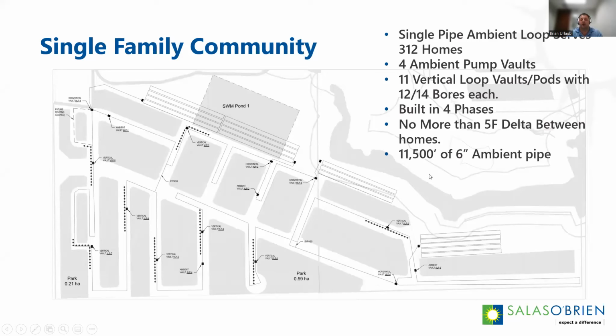Now there's about 2 miles of 6-inch ambient pipe. That ambient pipe picked up about 10% of the overall energy needed in the heating season for this system. So we were able to downsize our vertical heat exchanger by about 10%, because we calculated how much energy—even though it's closer to the surface and the temperature gradient isn't as good as if you're 20 feet below, you're still warmer than the temperature flowing through the pipe. So we're absorbing energy, not losing energy.